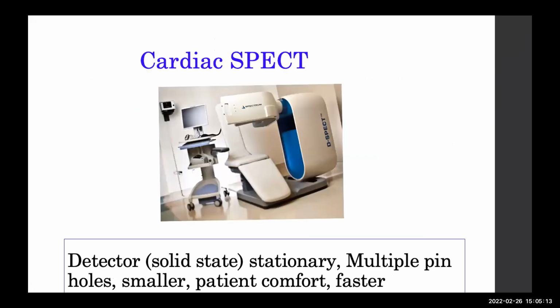This is another type of camera, the D-SPECT, where this is the detector system, with a fixed angle, where the detector is solid state, stationary, has multiple pinhole collimators, and is just focused. The patient is sitting on a chair, and this detector system is focused over the heart, over the chest of the patient, and the image finishes within 3 minutes, because of very high resolution, faster acquisition and high sensitivity crystals, which give you very crisp images within 3 minutes. This is a new technology, and many hospitals are now acquiring it if they have a high cardiac SPECT volume. So they are going for these systems.